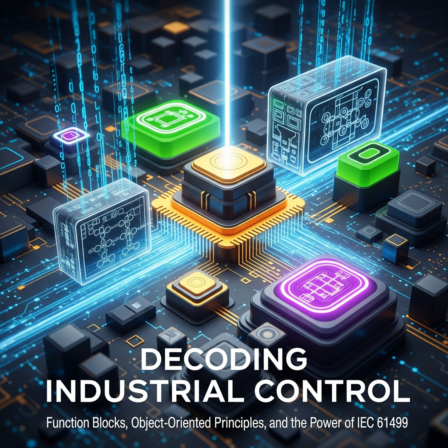Instead of having its own fundamental algorithms, its logic and control are defined by linking together other function blocks, could be basic ones, or even other composites. So it's like building with Legos. Exactly like that. You express its functionality through data connections and event connections between the components inside it. It lets you build up complex behaviors from smaller, reusable parts, a higher-level module, essentially.